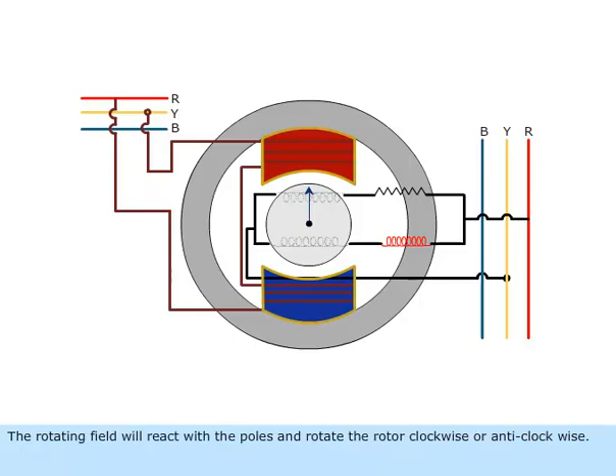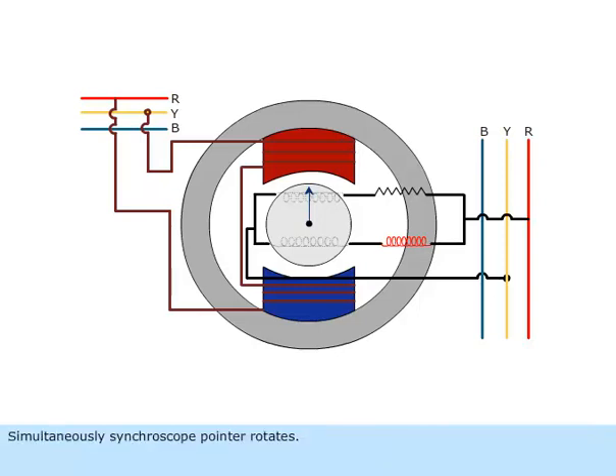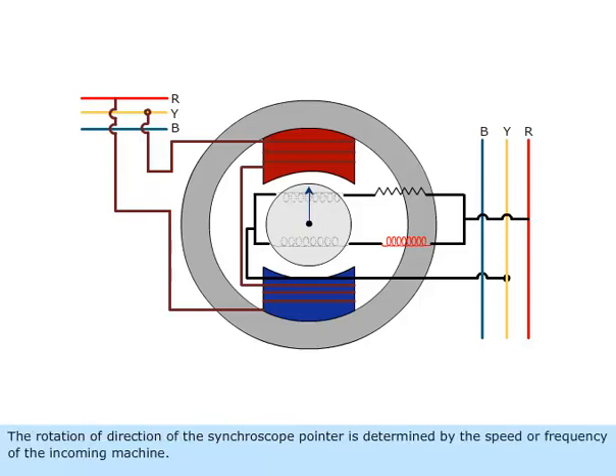The rotating field will react with the poles and rotate the rotor clockwise or anticlockwise. Simultaneously, the synchroscope pointer rotates. The direction of rotation of the synchroscope pointer is determined by the speed or frequency of the incoming machine.